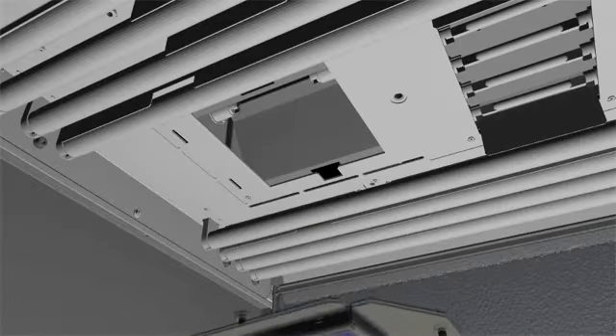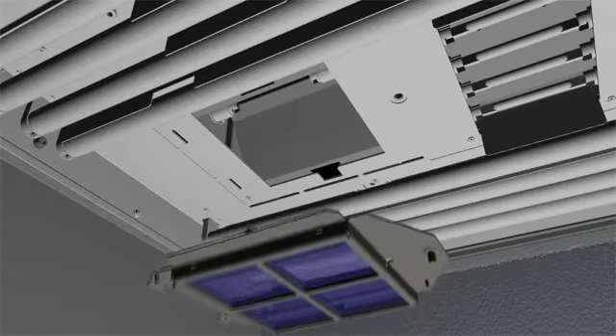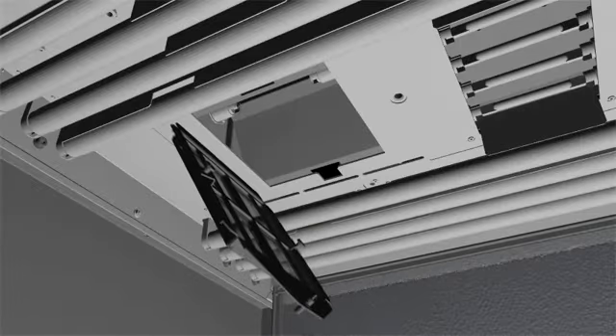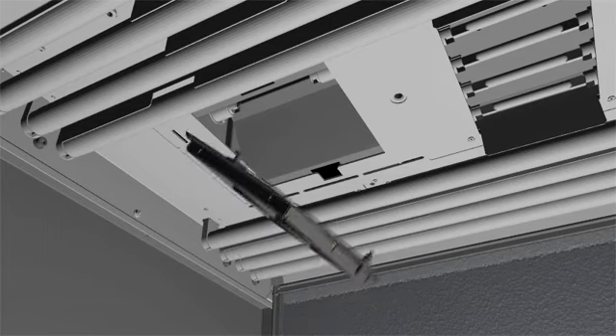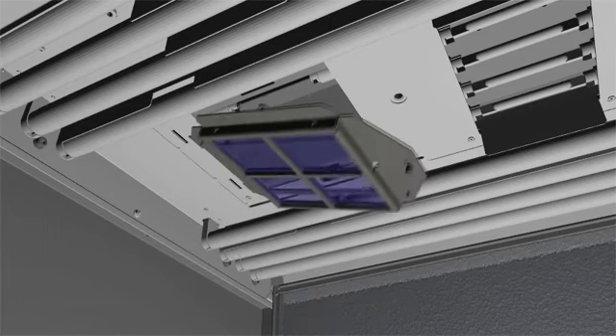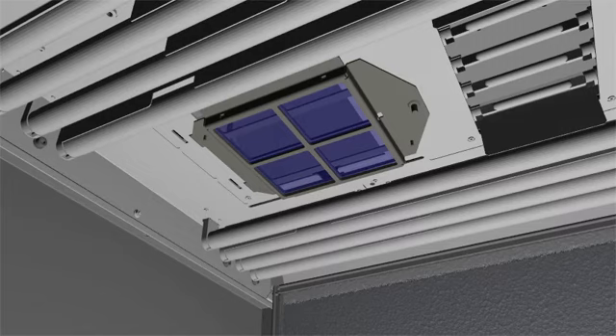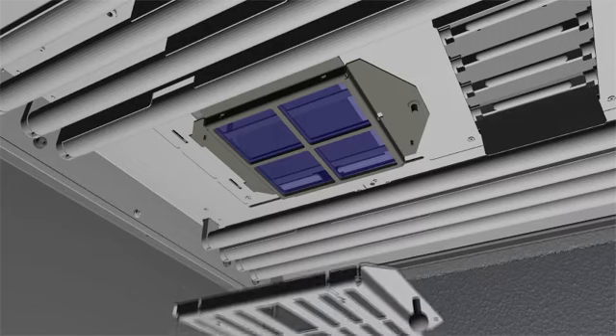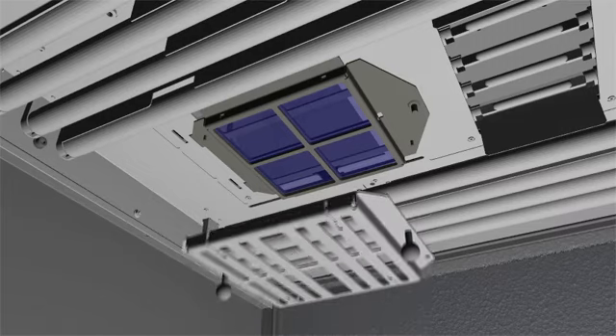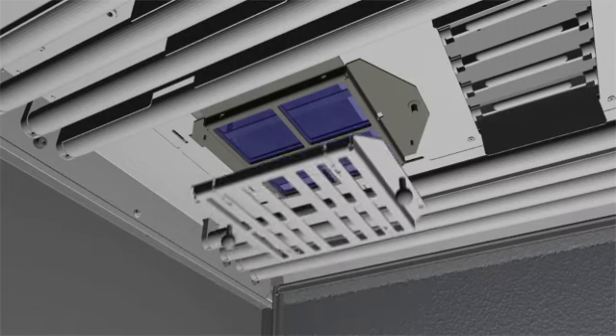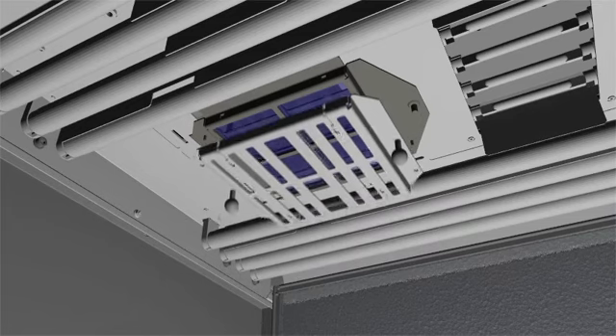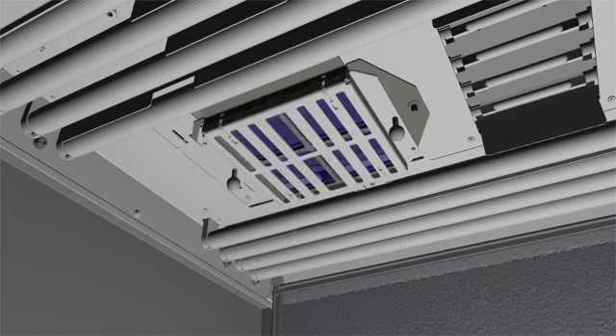Rotate the daylight filter pack back into place and push in on the fastener button to secure it. Repeat these steps for the other daylight filter pack. Finally, using the knobs, reinstall the attenuators on the filter packs. And you're done.